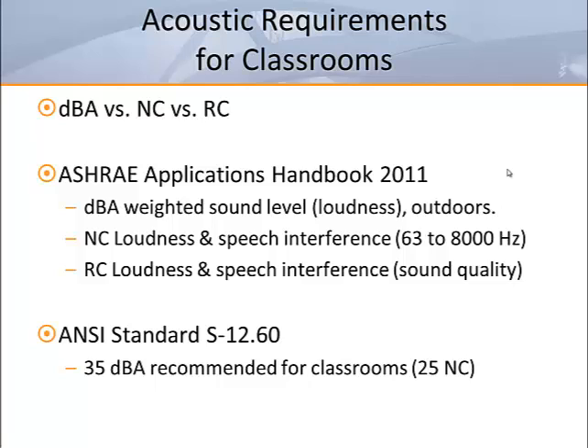ANSI Standard S12.60 recommends a background noise level for classrooms of no more than 35 dBA. There is no direct correlation between dBA and NC or RC, but most sources show that for comparing devices with mid-frequency range sound, 35 dBA is equal to an NC and RC loudness of approximately 25.